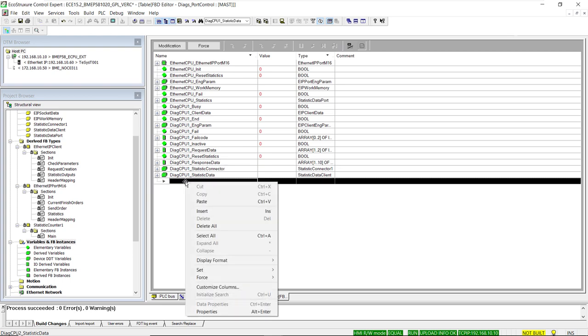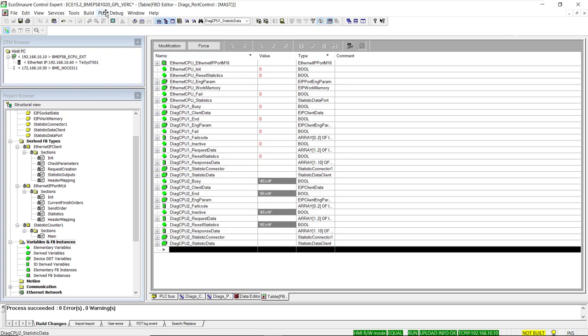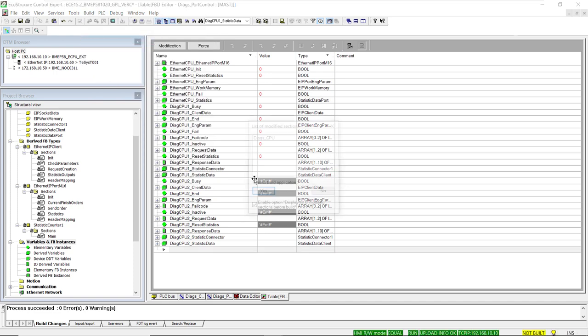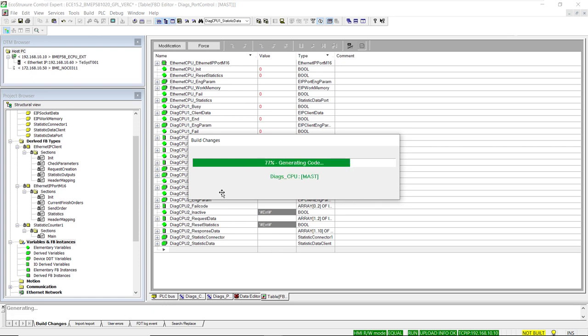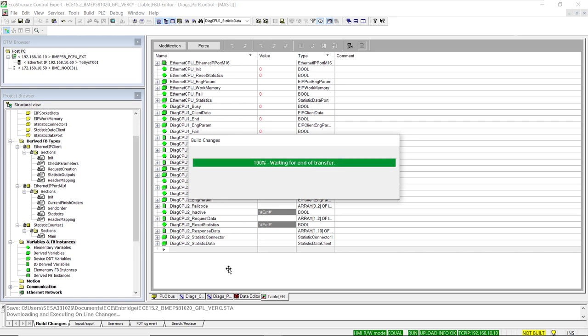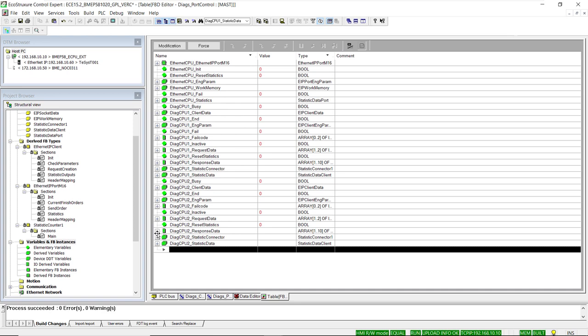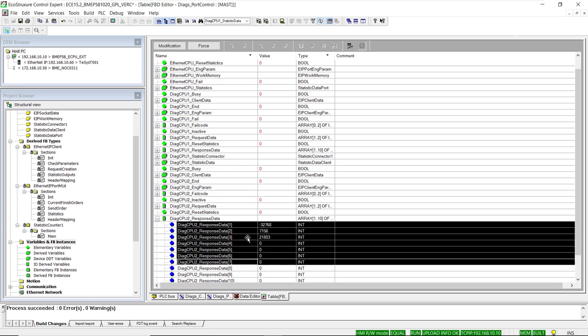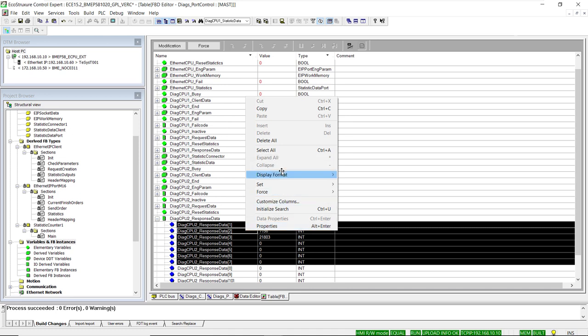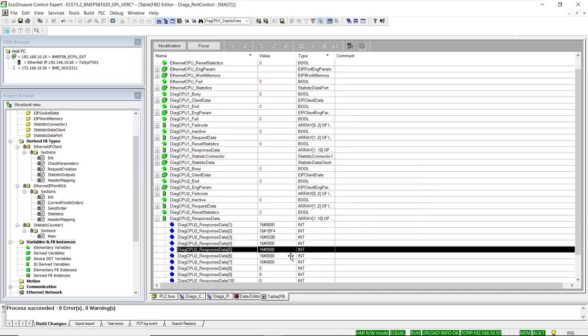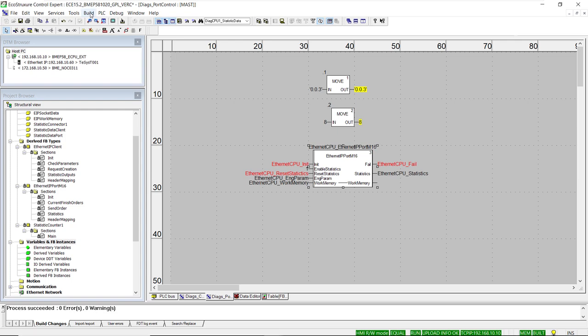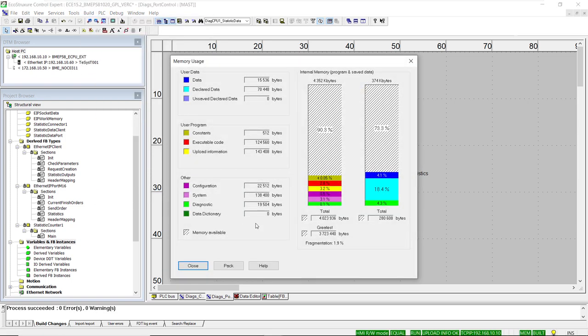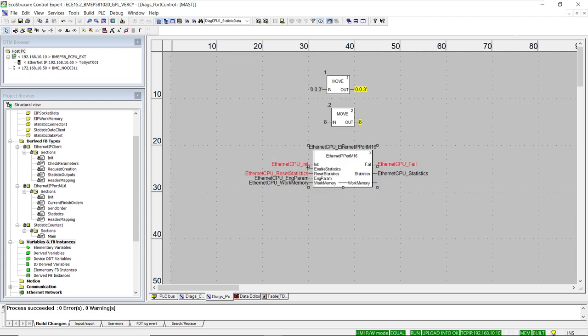We copy-paste the variable names into the animation table and build the changes, which are downloaded to the PLC since we are connected online. Once the download completes, we go to the animation table, set the display format to hexadecimal, and correctly view the MAC address octets of the CPU. Notice that adding the second Ethernet IP client function block instance barely affected memory: free space changed only from 78.6% to 78.3%.